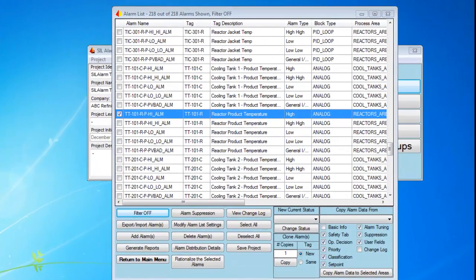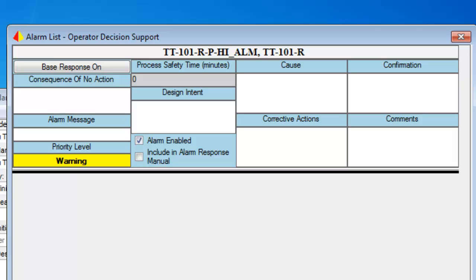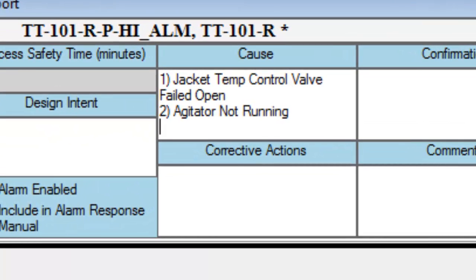To begin rationalization, we'll select the high temperature alarm from the list of alarms in our master alarm database, which was created by importing the alarm settings from the control system. We begin with a clean slate and will document all of the fields associated with alarm objective analysis. Let's start by defining the most likely causes for the alarm — we must be specific. Defining that the cause is simply "high temperature" is not very helpful. We want to know what could cause the alarm to occur to make sure it represents an abnormal condition. If the cause is an expected condition, then it probably should not be an alarm.